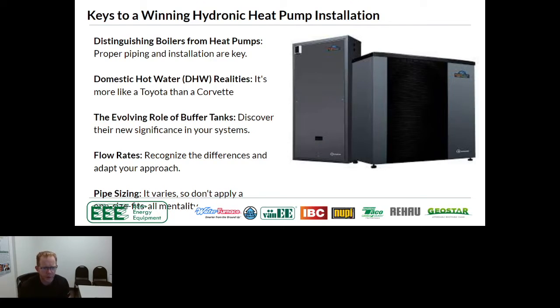As we look at a hydronic heat pump and some of the winning components to success, the very first thing we need to pay attention to is that we do not want to pipe them like they're a boiler, and we're going to talk about why. The other thing we have to be very careful about, and I've seen this over the last 2 decades I've been involved with hydronic heat pumps, is that you can do domestic hot water with a heat pump, but it's not going to be that Corvette experience that you would get with a boiler. We're used to hooking a boiler up to an indirect and having so much firepower that we can heat that indirect very quickly. We can't use traditional indirects as a general rule on hydronic heat pumps, and we need to think outside of the box when we apply this.